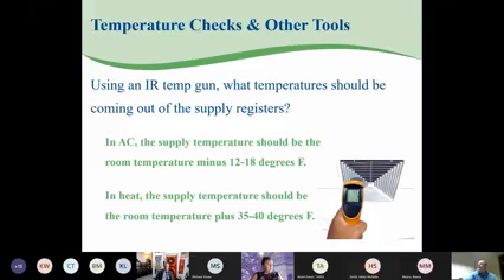against other factors. Other tools that can be used to measure your system's performance are a voltmeter, ammeter, electronic psychrometer to measure humidity and dew point, flashlight, IR camera, HOBO data loggers, which can then be downloaded to an Excel spreadsheet. Lots of different things can be logged with a HOBO data logger. There are books available to help us. There's a guide to energy management or handbook of energy audits that will give us ways that we can benchmark our building. You gather the information, chart it, and trend it, you can determine what's going on.